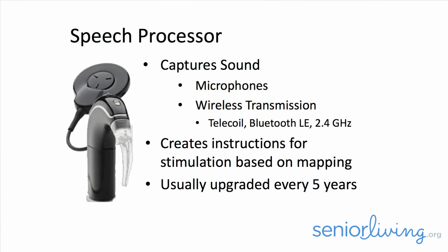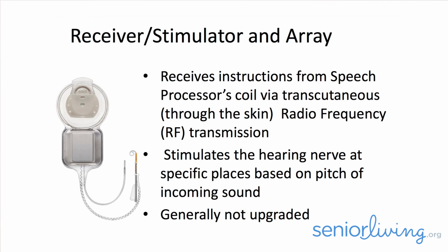Now those instructions are then sent to the internal device using radio waves that travel through the skin. So that small part at the end of the wire, that circular part, is called a coil, and that coil will actually attach itself to your skin using a magnet. On the inside of the skin is another magnet, and that part is called the receiver stimulator. So the coil and the receiver stimulator marry up using those magnets, and then those radio waves travel through the skin, providing instructions for the actual implant to then send a signal down that electrode array and fire in very specific locations and patterns so that your auditory nerve, or your hearing nerve, can actually get the signal up to your brain. So they're not that different, but in fact they are very, very different.